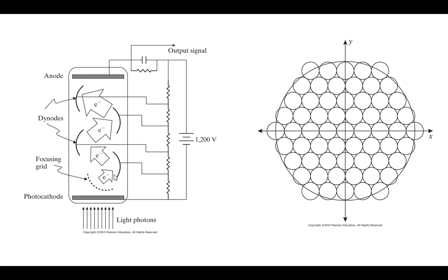An analog amplifier, and then they hit that anode, and you can see the capacitor that's on there, right? It'll filter it a little bit, and you've got a spike, and that spike is proportional to how many hit, which is proportional to how strong the photon hit here. If the photon had more energy, it'll release more electrons to go through this whole sequence. Since the amplification is constant, the number of electrons that hit the bottom is proportional to how strong the photon was that came in. So you've got a good measure of what it is. That's basically how a photomultiplier works. Good?